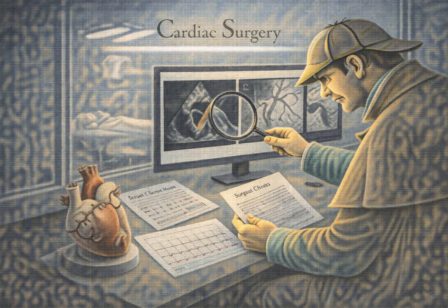And is there a pump that sucks the blood out? You'd think so, but usually no. We just use physics. Gravity. The bypass machine itself sits lower than the patient on the operating table, so it acts as a siphon. The dark, deoxygenated blood just flows out of the body and into the reservoir of the machine. Okay, so now the heart is empty, the blood is in the machine. What happens to it there?